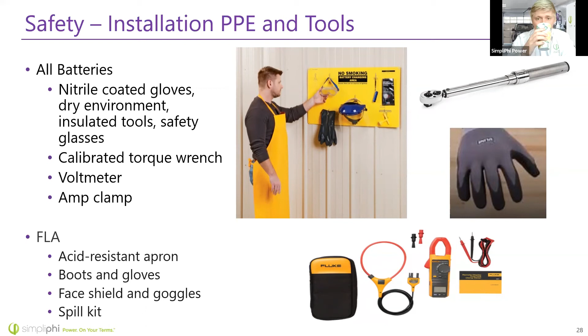Once you have finished all of the wiring for your system, here's a good guide you can use for commissioning, the order of commissioning. What should I connect to what first? First off, make sure your breaker is off during installation until you're ready to fully commission the system, and be careful not to short the terminals while you've got the breakers on. Never connect 2 batteries at a significantly different state of charge. This is going to result in not a good balance between the batteries during operation, and then also a rush of current from one to the other. This is especially a concern when you're adding a battery to an existing bank. So when you're adding a battery, you want to make sure you charge up the existing bank fully, disconnect it, then connect that new battery to the charger, charge it up fully, and then you can connect it.